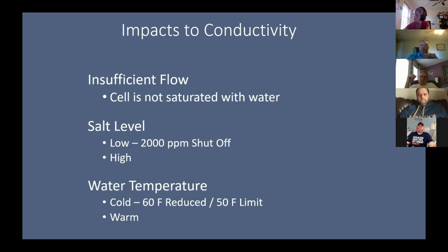In regards to salt levels, low salt levels will shut it off at a certain point. But when you're coming off of what you would normally maintain, let's say 3,000 parts of salt, as the salt level starts reducing, it impacts the amount of chlorine that's produced. So when you're losing salt and you don't know it, there's a tendency for you to go out and increase the output percentage, not realizing that you're low on salt, and that lower salt level creates less chlorine itself, okay?